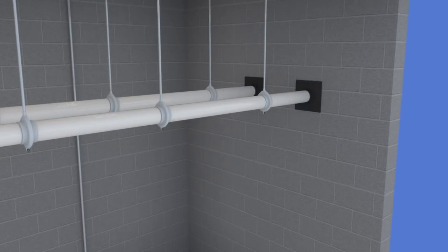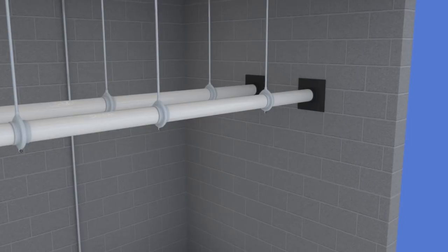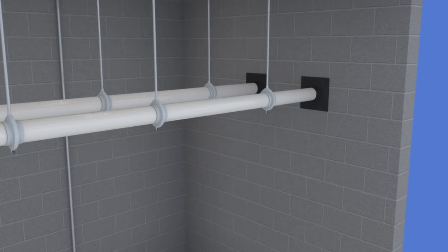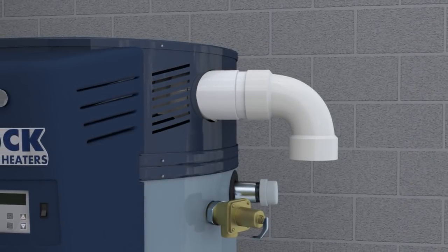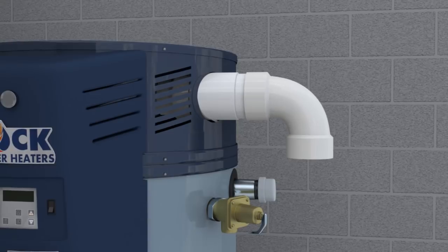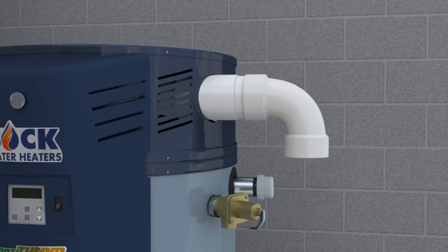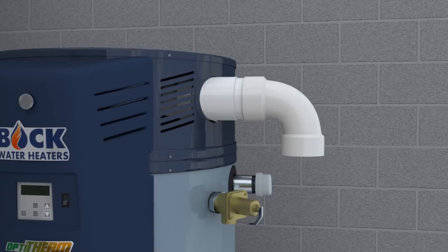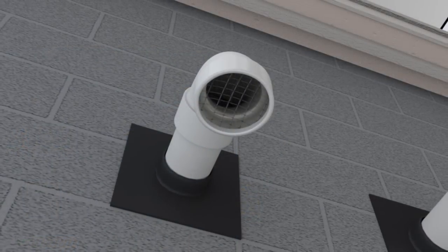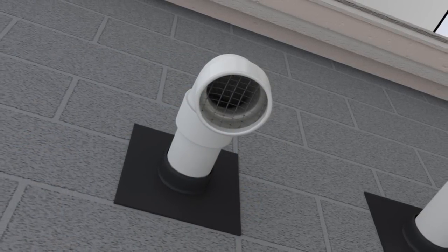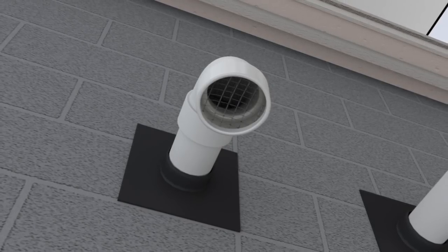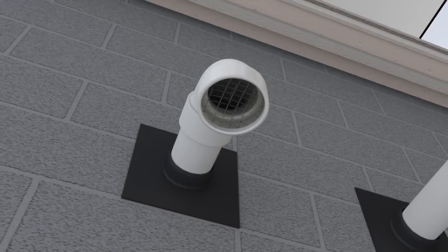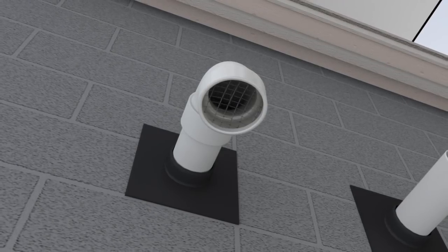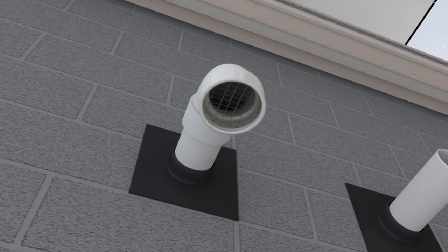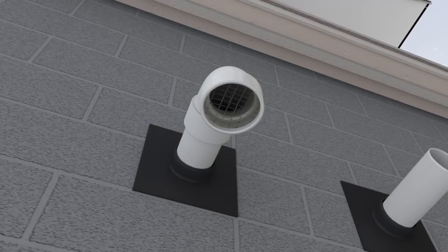Support all vent and combustion pipe according to state and local codes. At a minimum, the pipe should be supported every 4 feet. A 4-inch PVC 90-degree standard bend elbow is supplied and must be used as the combustion air intake termination fitting for either a direct vent or power vent system. A supplied low-resistance protective screen to block foreign debris or small animals from entering the vent comes installed in the termination elbow. Although not supplied, an additional low-resistance screen can also be installed in the exhaust termination.